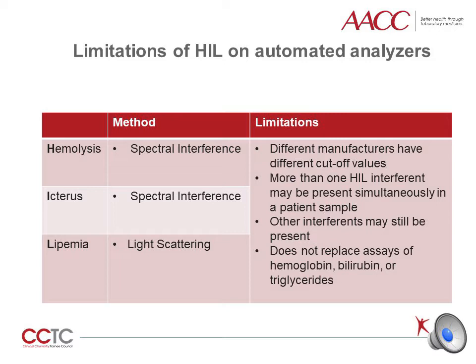There is an overlap in the spectra of hemoglobin, bilirubin, and lipemia. While there is no currently defined best method for measuring serum indices, manufacturers' product inserts may provide useful information on how the interferences were assessed. More than one HIL interference may simultaneously be present in a patient's sample. The presence of one HIL interference may adversely affect the measurement of another HIL interference. Non-HIL interference may also be present. Examples of such interference include methemalbumin, beta-carotenes, dyes, and contrast media present in the blood.